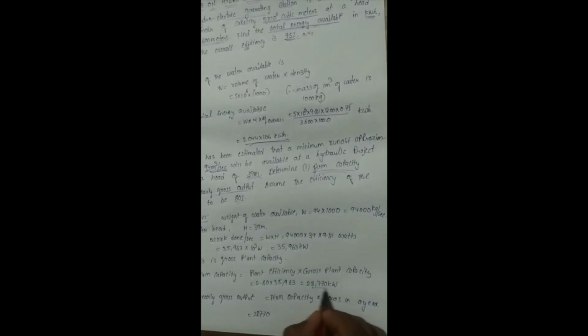And the yearly gross output is equal to firm capacity into hours in a year. That is equal to 28,770, which I had obtained from here, into 8760. This is the number of hours in a year. This is equal to 252 into 10 power 6 kilowatt hour.